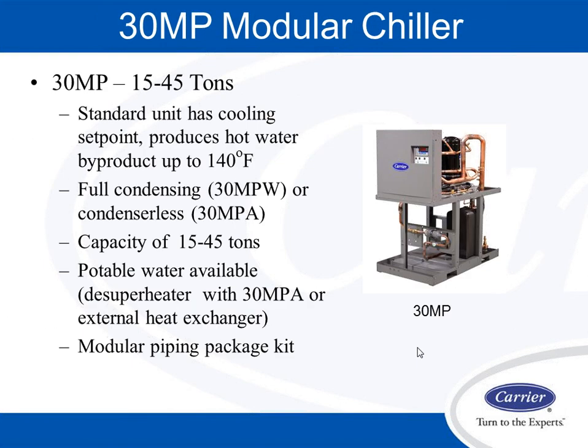The 30MP is a great little product that Carrier launched a couple years ago, and it's a modular design from 15 to 45 tons, standard cooling operation, but it can operate and produce heat up to 140 degrees standard without any issues at all. You can do full condensing water cooled, or you could team it up and put some remote condensers on a roof also. The heat reclaim, you can use it for potable water, or you can use it for reheat.